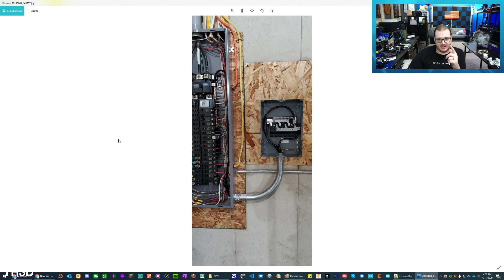I did mark the neutral here, though I hadn't marked it before — I just remembered which one it was. So here are my two phases, and my ground going to the bus bar. This ground isn't bonded to the neutral since it's a sub panel. I've got my 100 amp breaker at the bottom for this sub panel, using 2 gauge copper wire. Here's my neutral lug, and this is where the big CT clamps go.